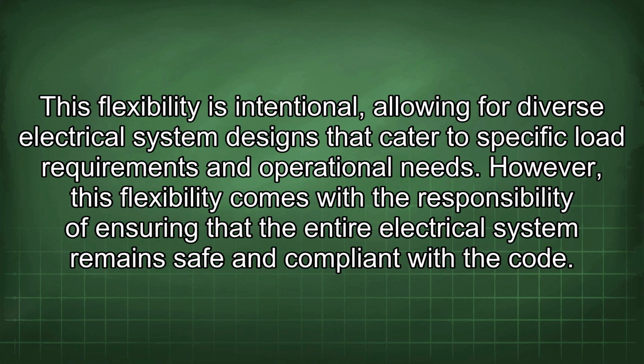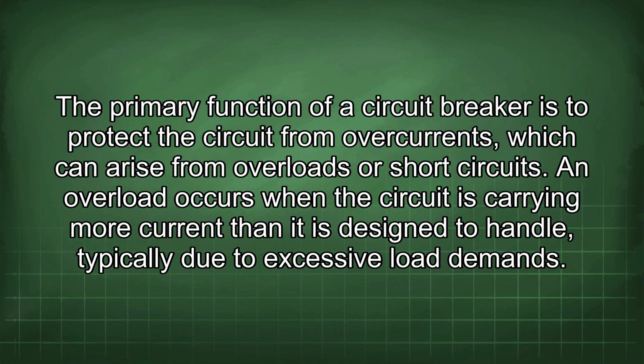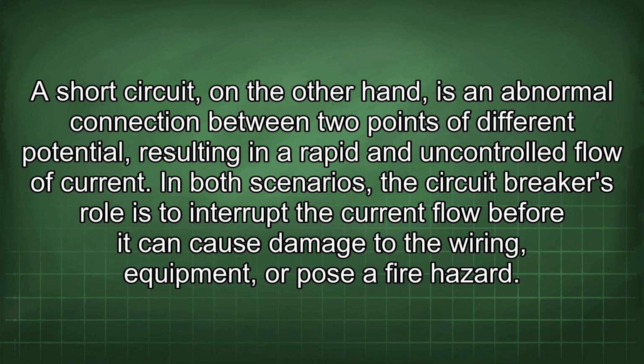However, this flexibility comes with the responsibility of ensuring that the entire electrical system remains safe and compliant with the code. The primary function of a circuit breaker is to protect the circuit from overcurrents, which can arise from overloads or short circuits. An overload occurs when the circuit is carrying more current than it is designed to handle, typically due to excessive load demands. A short circuit, on the other hand, is an abnormal connection between 2 points of different potential, resulting in a rapid and uncontrolled flow of current. In both scenarios, the circuit breaker's role is to interrupt the current flow before it can cause damage to the wiring, equipment, or pose a fire hazard.